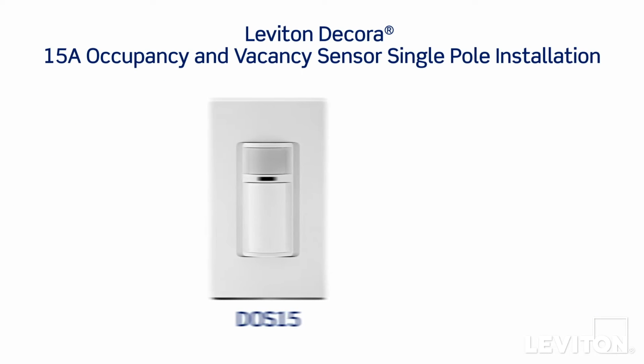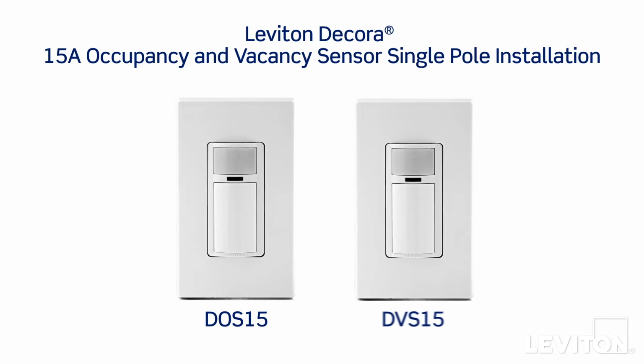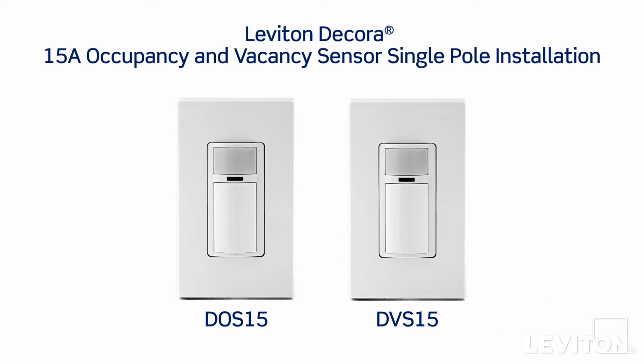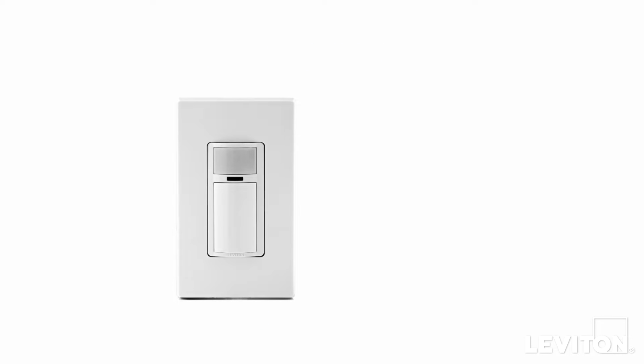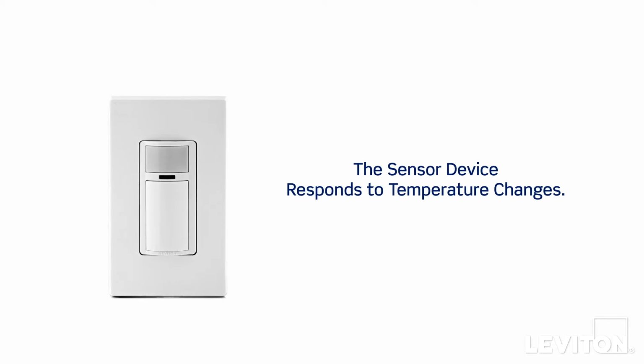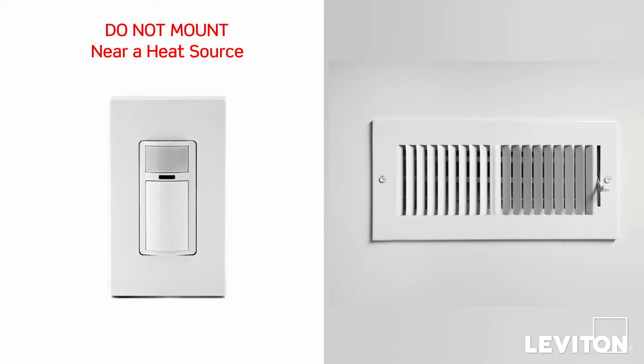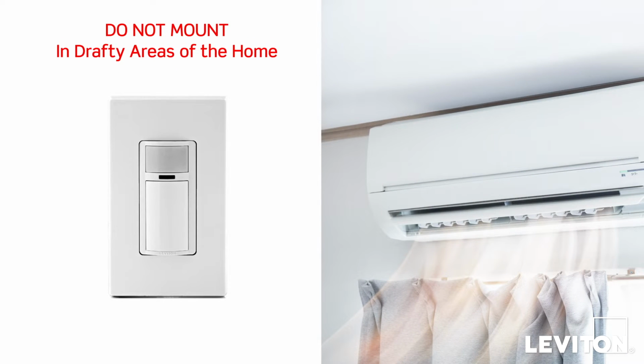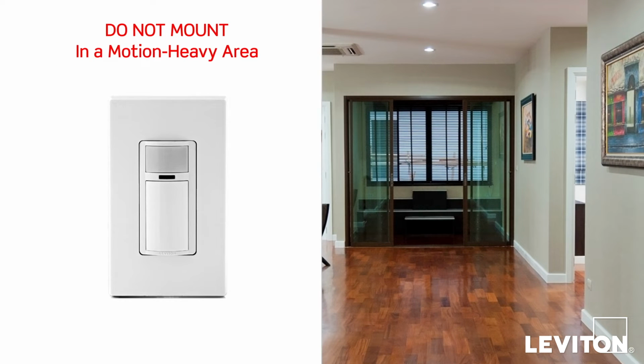This video will demonstrate how to install the Leviton DOS15 and DVS15 Decora 15-amp occupancy and vacancy motion sensor wall switches. It's important to note that the sensor may respond to temperature changes. Therefore, do not mount near a heat source, in a location where hot or cold drafts will blow directly on the sensor, or where unintended motion will be within the sensor's field of view.